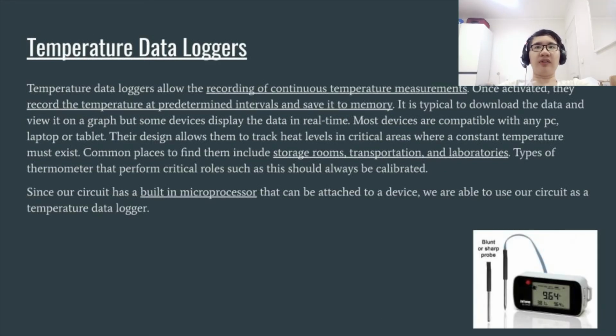Temperature data loggers allow the recording of continuous temperature measurements. Once activated, they record the temperature at predetermined intervals and save it into memory. It is typical to download the data and view it on a graph, but some devices display the data in real time. Most devices are compatible with any PC, laptop, or tablet.